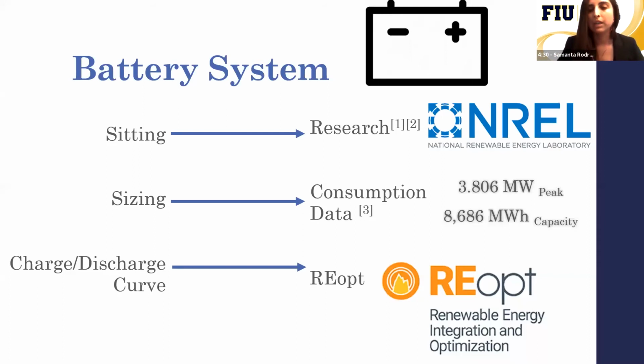For the power capacity, we selected 9 megawatt hours that are able to supply up to 3 continuous hours at the power rated. For the charge and discharge curve, we use REopt.